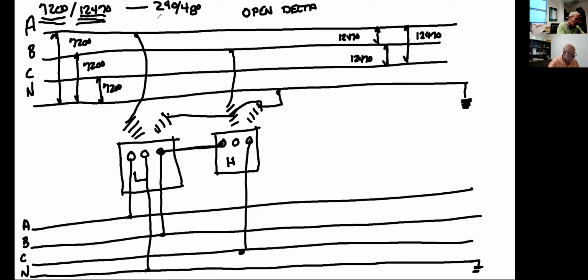The only thing that's left now is voltages. Okay. So from A, it's just like the primary, A to neutral, B to neutral, C to neutral. You got to be careful here. This is a high leg. Remember, this transformer is a high leg. From A to neutral, what's my voltage? 240. From B to neutral, what's my voltage? 240.